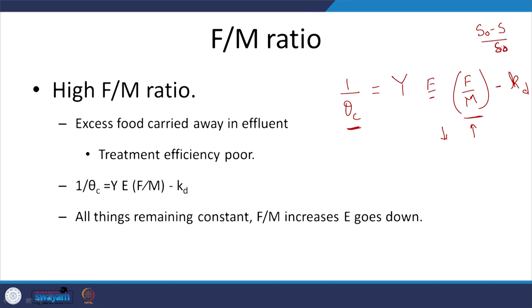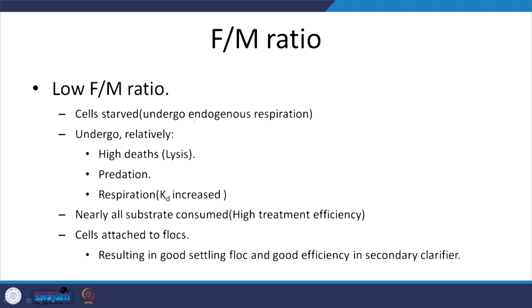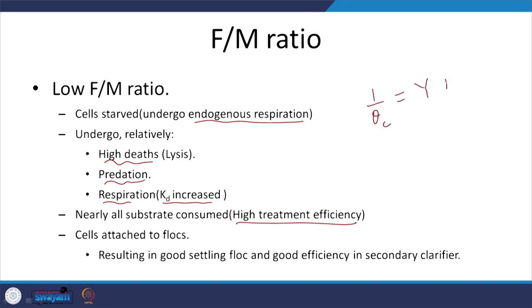With low F/M — low food and relatively more microorganisms — the microbes are starved. There may be some endogenous respiration, but you are still providing waste or substrate. This leads to relatively high deaths and more predation, so KD increases. Nearly all substrate is consumed, giving high treatment efficiency. The equation is: 1/theta_c equals yield times efficiency times F/M minus KD.